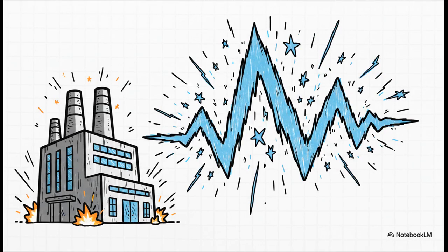So what does that actually look like on paper? When a fault hits one of these traditional systems, the subtransient current, the current in those first few critical milliseconds, absolutely skyrockets. It jumps to 4, sometimes even 6 times the normal operating limits, bursting out in a violent, asymmetrical, decaying wave. And here's the kicker: our entire global power grid safety systems were designed over the last century to look for exactly this massive 600% spike.